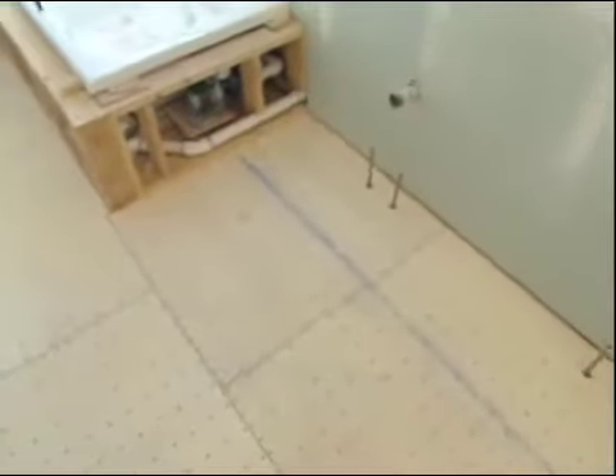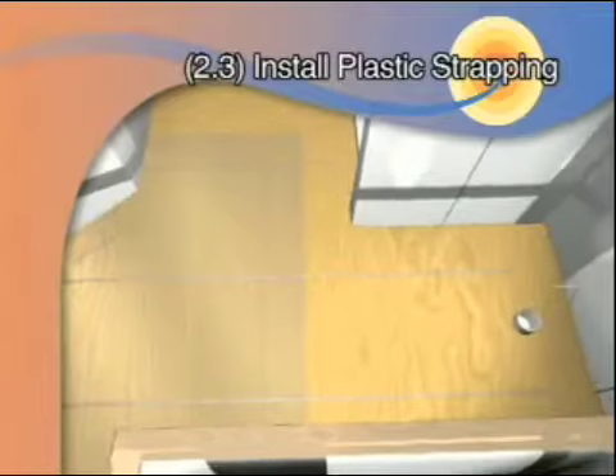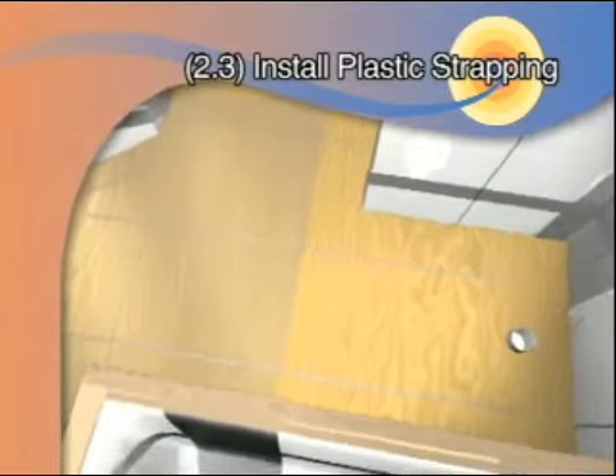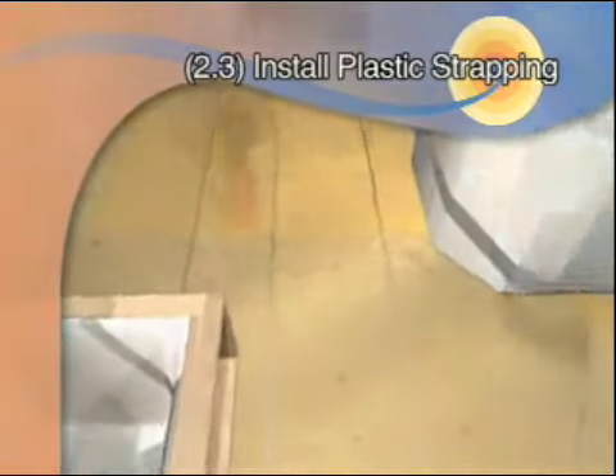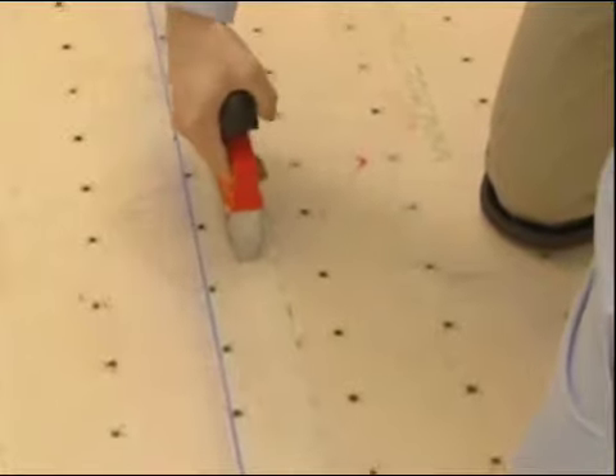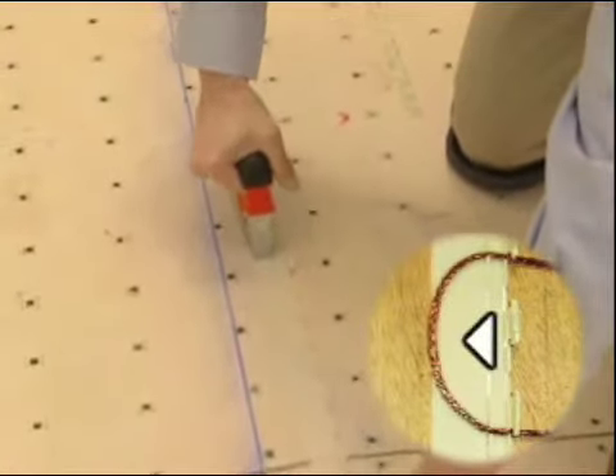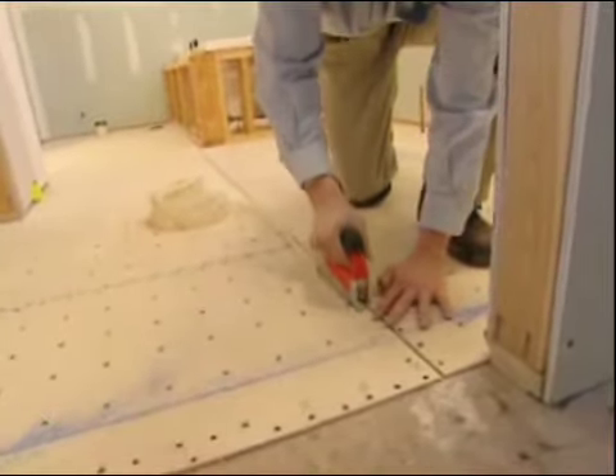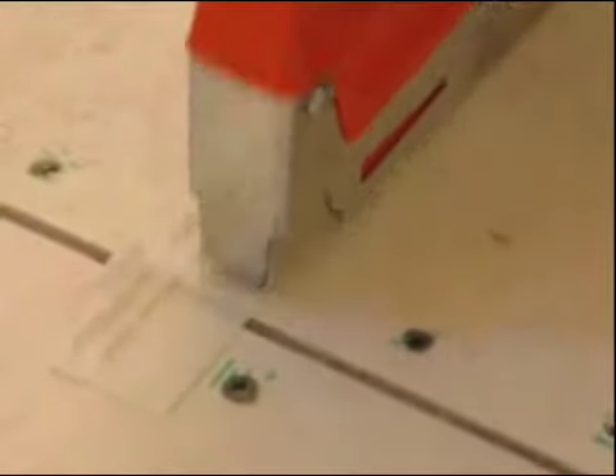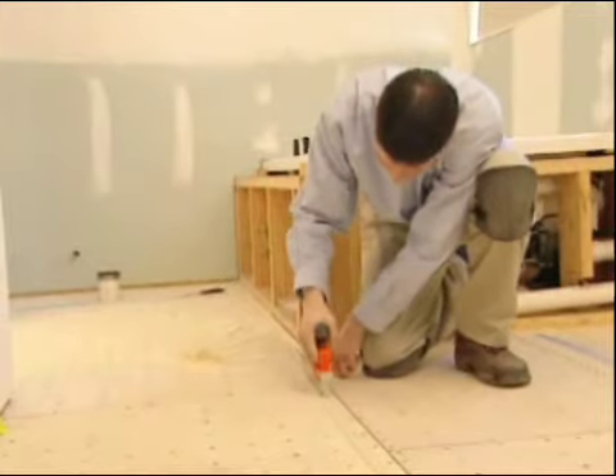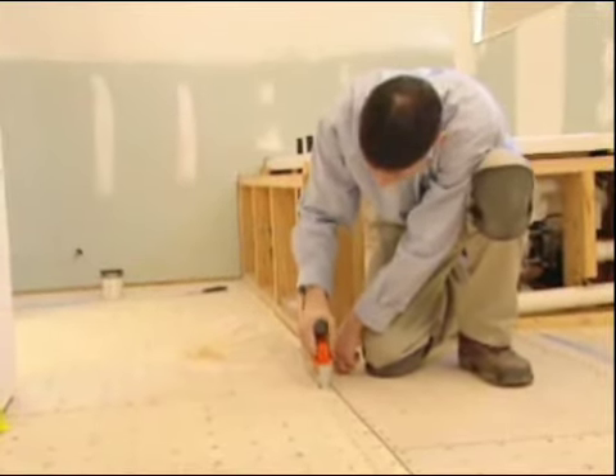The floor should be free of debris and other obstructions that may damage or cut the cable before you start installing the strapping. Install the strapping onto the floor following the planning sketch. Note, strapping is positioned so the tab clips close towards the outside of all cable turns. Begin stapling the strapping at one end by sliding the staple gun along the strapping length. Staples should be spaced no more than 6 inches apart. Ensure the strapping is snug against the floor.